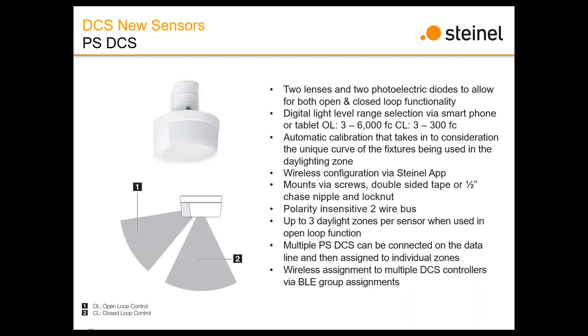Great question. The 24-volt devices are separate and don't communicate digitally, which is why we made digital type sensors. For example, our Dual Tech or Quattro HD sensors look identical, except they connect onto the bus. Every single sensor and presence detector we make has the photo cell, and yes, you can use it within those spaces. However, it's very common that the best location for a sensor isn't the best location for a photo sensor, which is why we have the two separate cases. But in a small room with only a single daylighting zone, you absolutely can use the photo sensor in our regular presence detectors to achieve that.